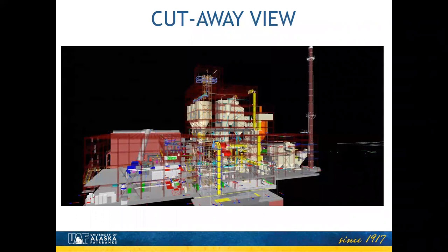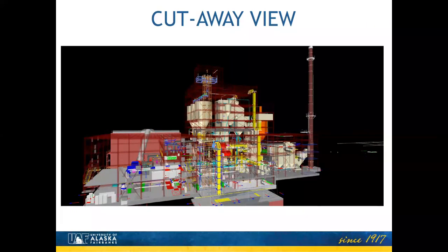So with the skin peeled back off the building, this is what it looks like. On the left-hand side of the screen, you're seeing the steam turbine generator building. It's a three-story structure that houses a lot of electrical switchgear, cooling water pumps. And then on the next floor, the steam turbine and generator itself. And on the floor above that, the control room that the whole plant is operated from. In the background of that, the larger red square is the air-cooled condenser, and that takes the steam out of the back end of the turbine after it's exhausted its energy and converts it back into condensate for reuse and recycling back into steam.